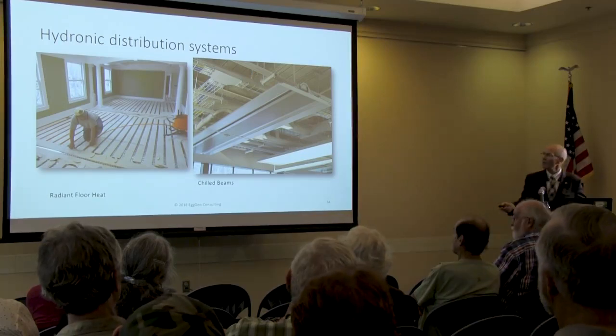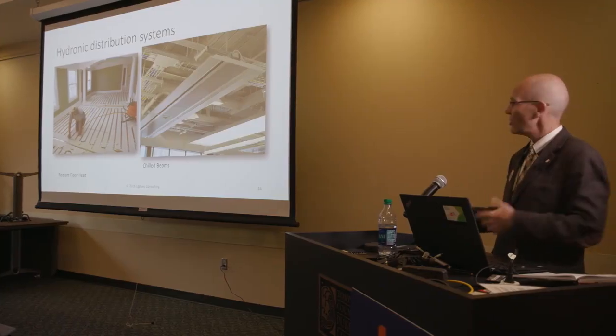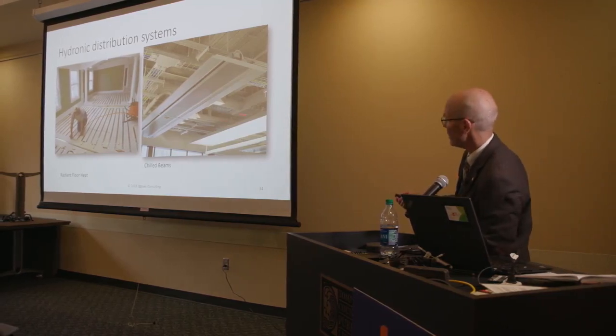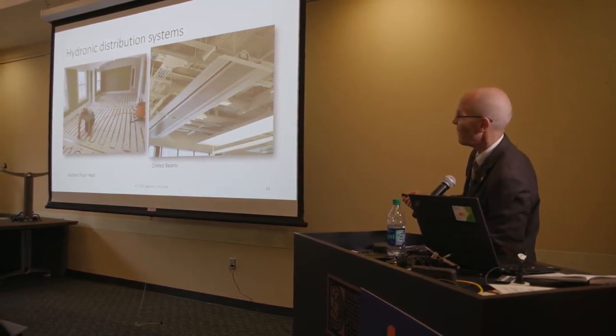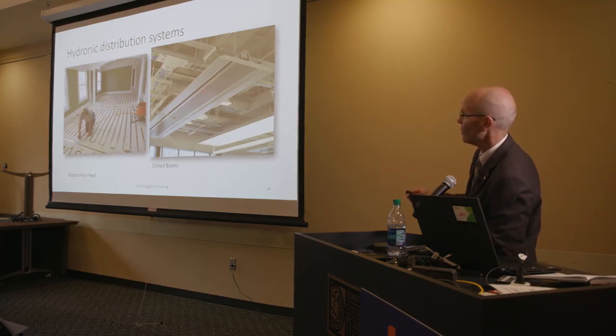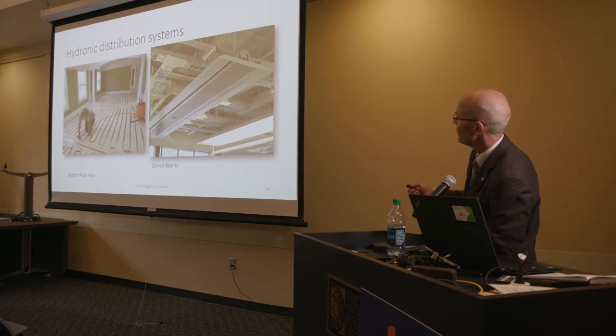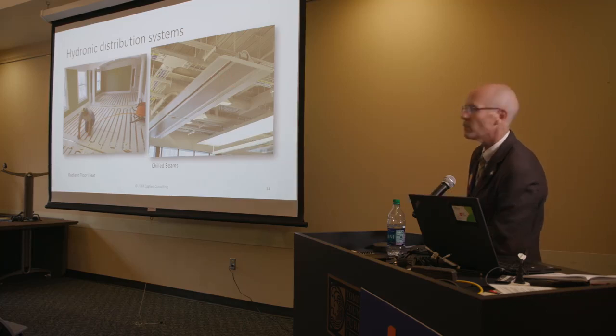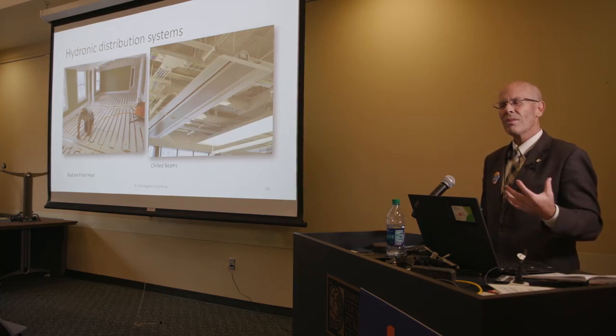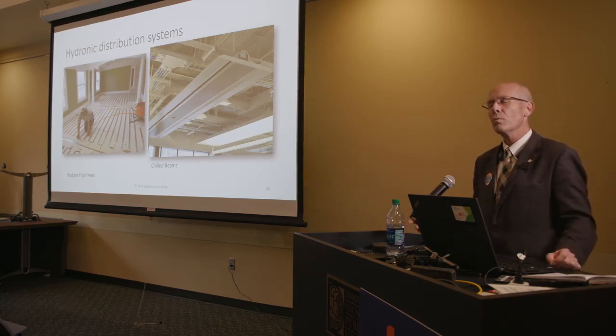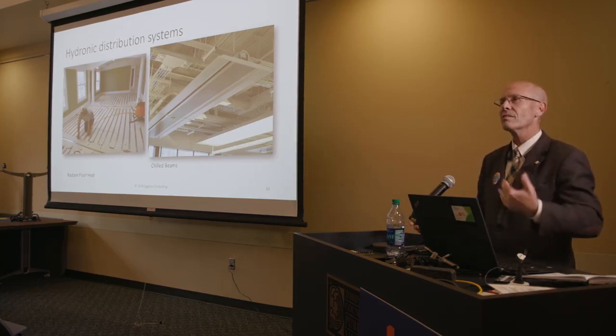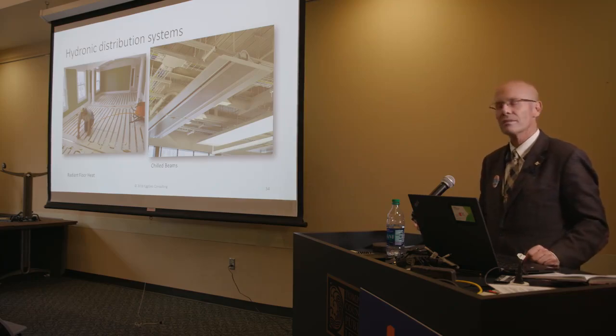So comfortable. Now, you may be wondering, you have to have fresh air. Well, if you look here, they have a dedicated fresh air unit providing about 1/10 the forced air normally. So this is what's called an active chill beam. You see this center vent, and some of the fresh air comes through that, but these louvers on the side are the radiant, and it's just like a cool blanket. It's constantly amazing.